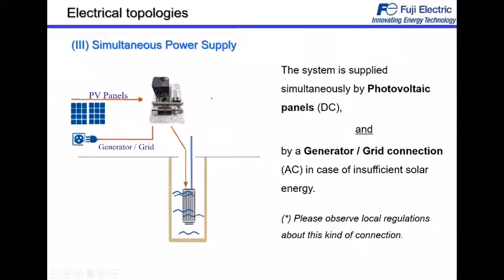The third one, I believe this could be very interesting, is the simultaneous power supply. Simultaneous means we have energy coming from PV panels, and at the same time the inverter is watching the energy from the panels, and if we don't have enough energy, not enough irradiation, then we take energy from the grid or from a generator. So the drive can automatically take energy from where it believes is the most efficient system. If we have enough, we take from the panels, if not, from the grid or generator.